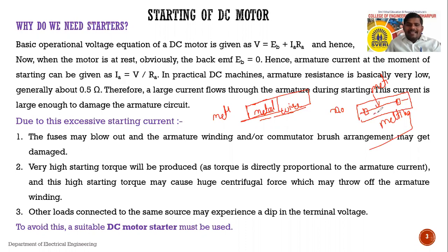See, it will carry only a limited amount of current. Once the current flowing through that wire exceeds the rated current, it will start melting, and once it melts, it will break. That means protection. Suppose our motor has a 10 ampere rated current and a fuse with a rating of 12 ampere is used. If the current exceeds 12 ampere, say the current flowing through the wire is 40 ampere, at that situation it will start melting and break the circuit, that means it will protect the motor.